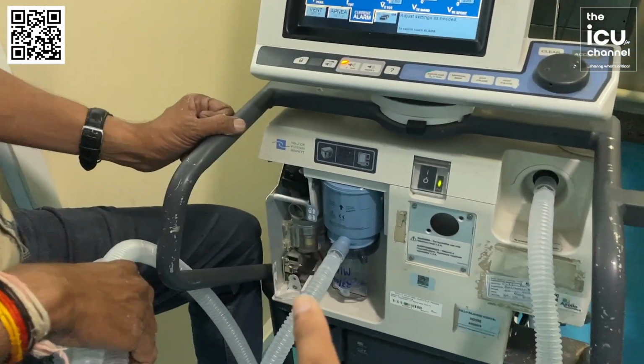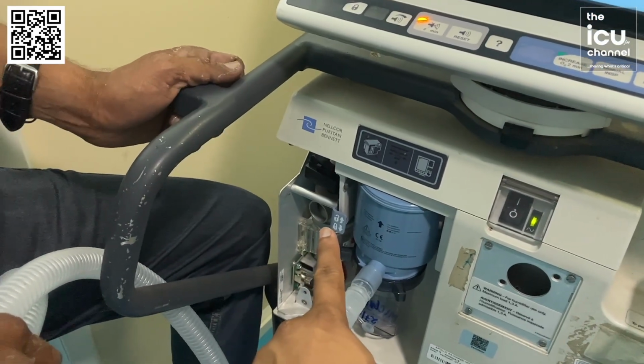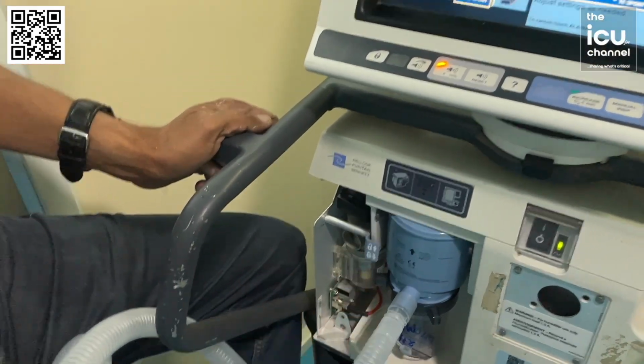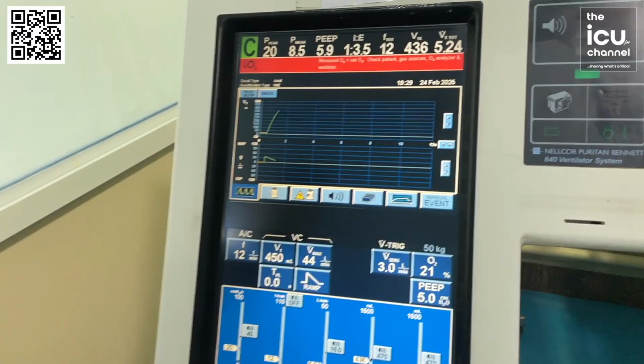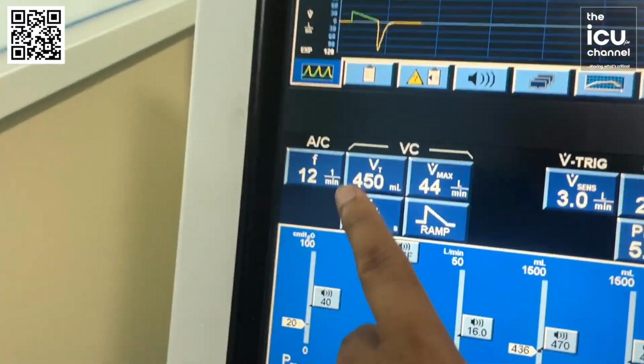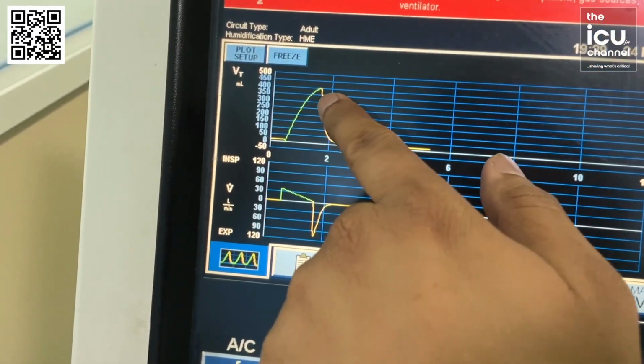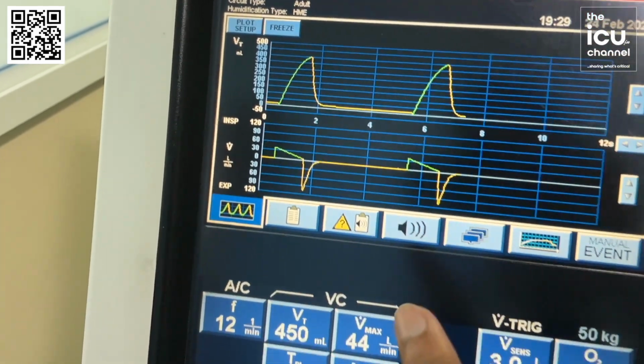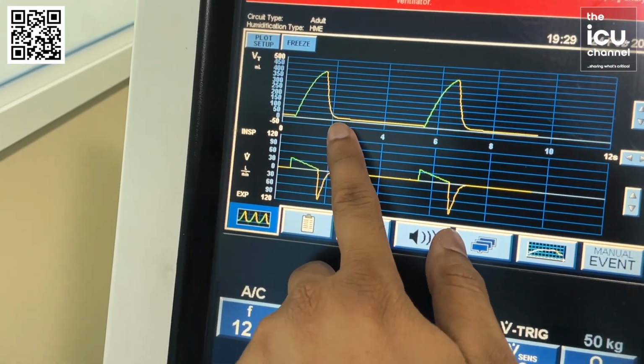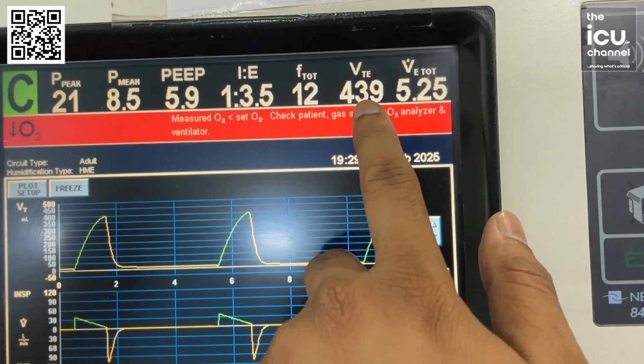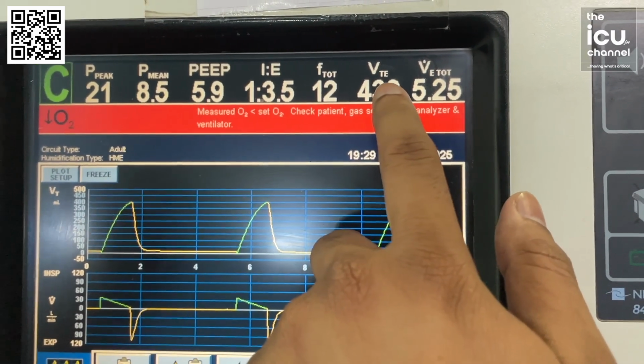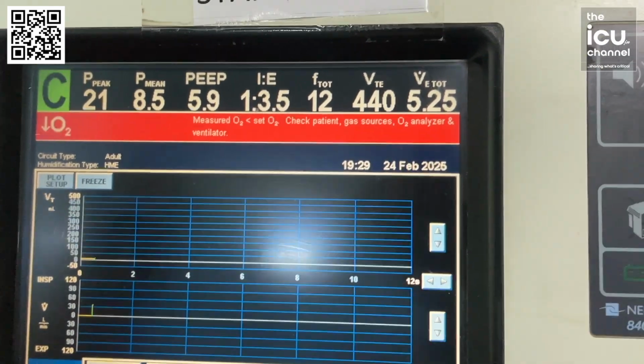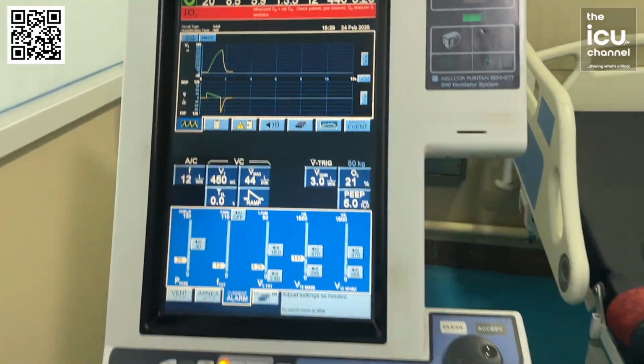One thing, and the second, it can also be an error of the expiratory flow sensor. So you need to figure out where the problem is. So this 450, you need to check it in the inspiratory limb here, and the expiration part you need to check either on the expiratory graph or the expiratory limb here, expiratory value here, expiratory tidal volume here.